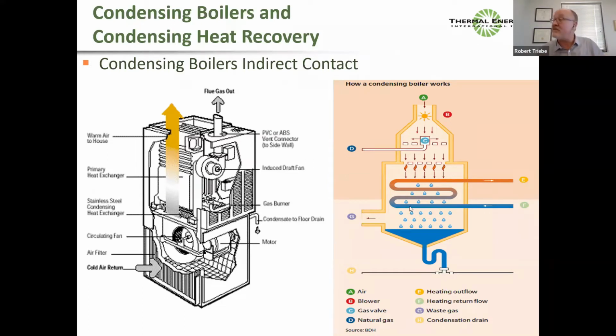So on the outside of the tube, this water, that's not your heating water, that's not circulating water, that's the water you're condensing from the flue gas. So that water becomes a separate stream that you can sometimes return to process or sometimes you put to drain. But your condensation happens on the outside of the tube. The heat is transferred to the inside of the tube, but your heating medium is separated from your flue gas. So that's an indirect contact condensing boiler.